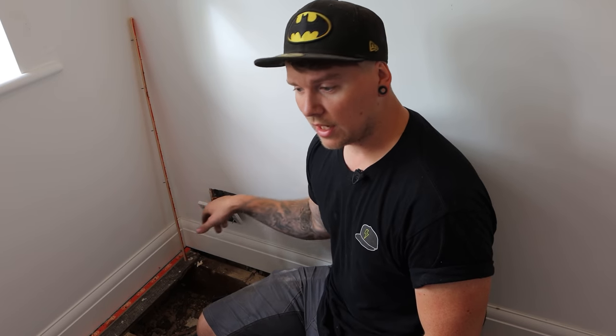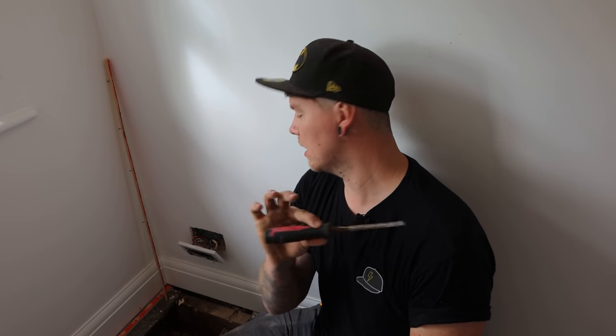All these socket boxes, like downstairs, are being reused. We've got no pull. We found spare cable clips in the floor, which Adam's found down here. There's quite a few, which looks like to us that someone's just clipped the cable to the wall. There's no conduits, no cappings, we can't pull stuff through. There's old cables, there's a new cable, there's a new socket been attached over here.